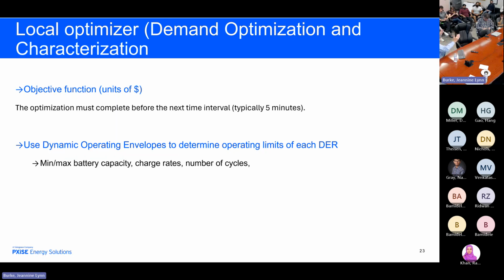So now we solve that for 24 hours, but we only issue commands for the next 5 minutes. Why do we only do that? Well, it's the standard MPC approach. You do the whole optimization, you execute now, and then you wait 5 minutes and you execute the optimization again, because your forecast can change. Now, that's another issue. What kind of forecast are we talking about? We're talking about the net load forecast. Where do we get the net load forecast? We have to have a weather forecast, plus we have to have historical data.